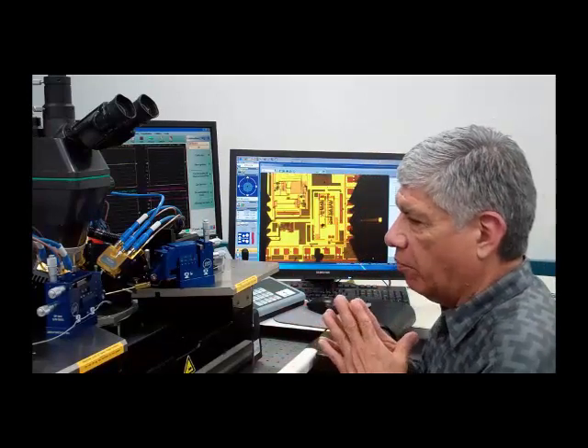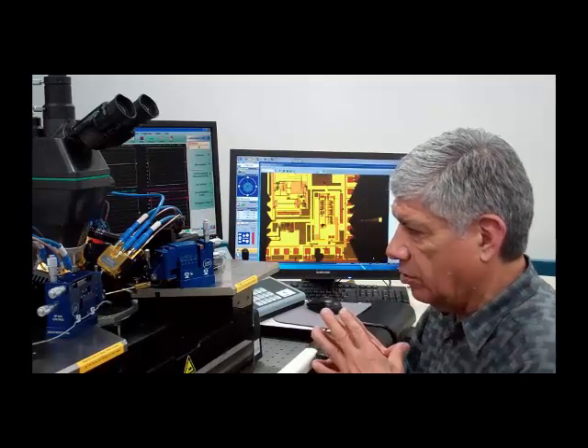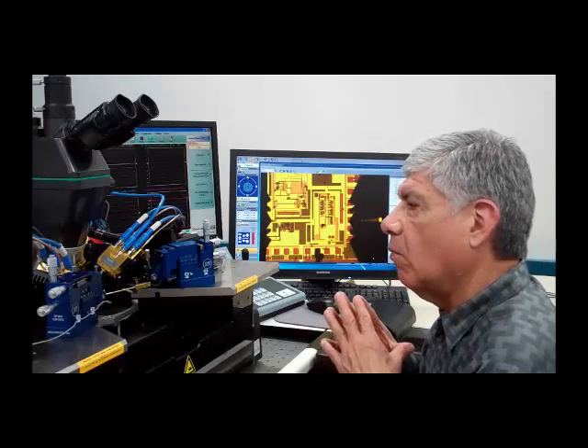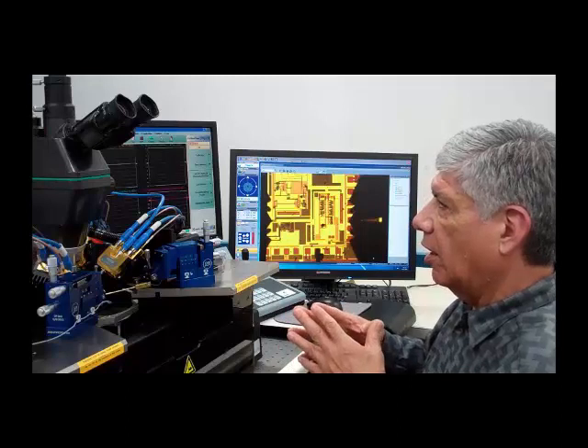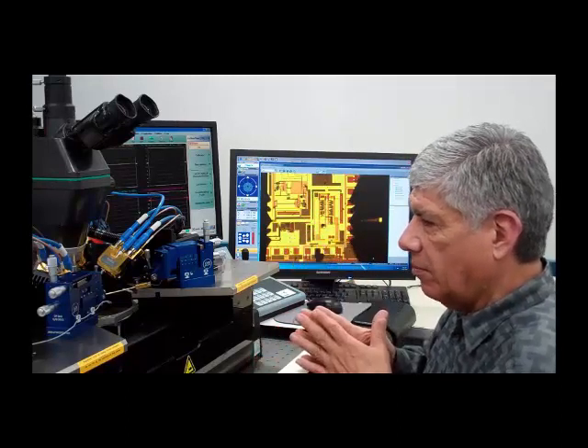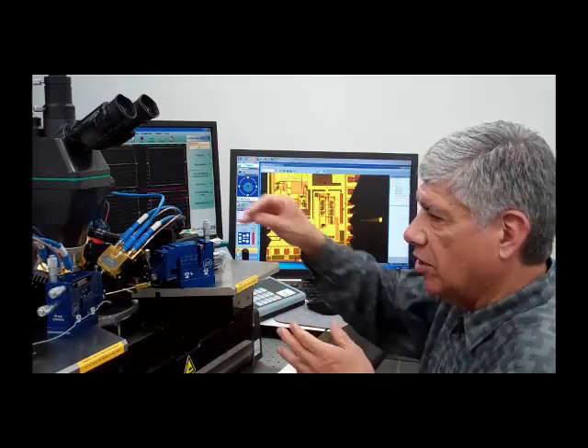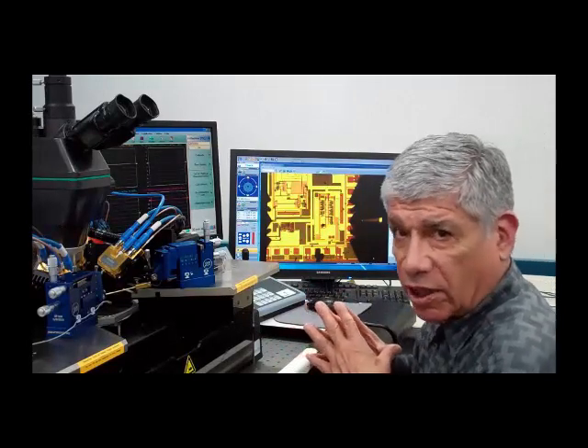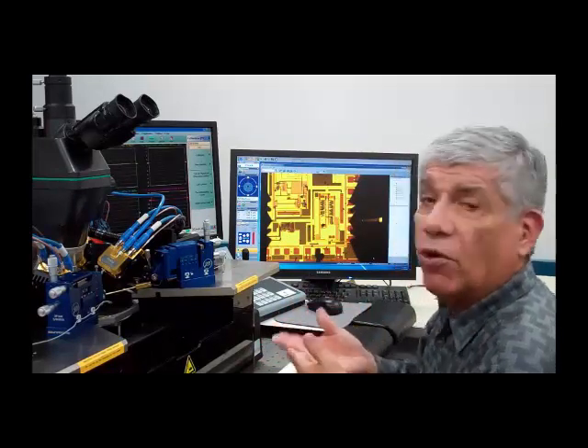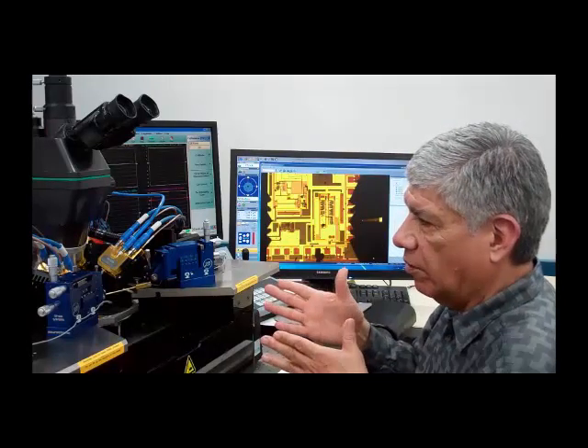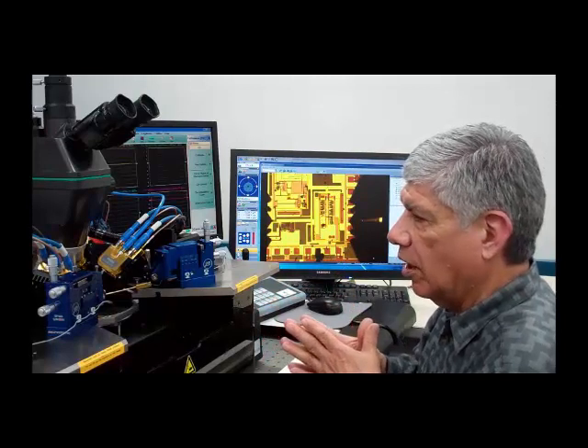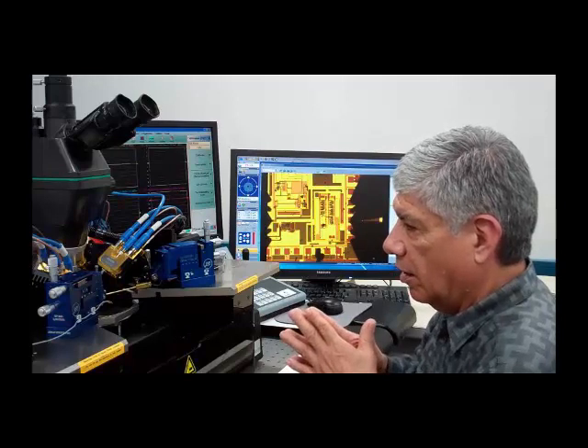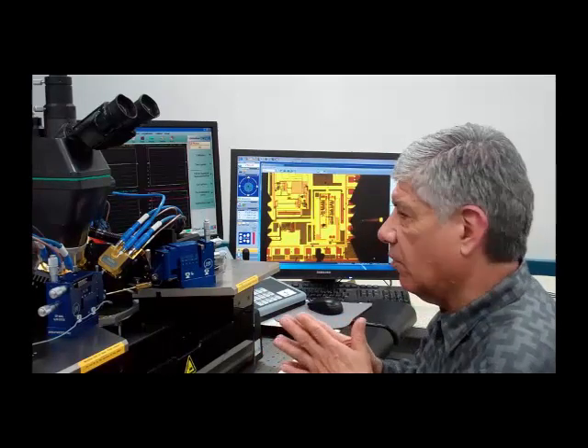The other thing that we are providing with VectorStar these days is the ability to do things like differential noise figure measurements. We are now able to do differential noise figure up to 70 gigahertz in the baseband system and up to the millimeter wave frequencies using the millimeter wave receivers. In the nonlinear transmission line modules, we're able to bypass the couplers, which are typically found in millimeter wave modules, in order to improve on the noise figure of the receiver. And so with that special receiver capability option, we're able to do differential noise figures up to 110 and even 145 gigahertz. So that is something that's being considered and thought of as being quite valuable in the ability to characterize differential LNAs, for example.